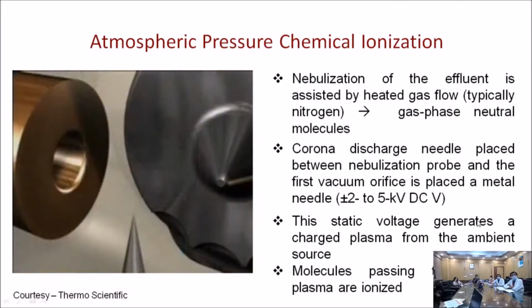In atmospheric pressure chemical ionization, or APCI, the LC eluent enters the source via a grounded capillary and is converted into an aerosol by concentric gas flows. The mobile phase and sample are transferred into the gas phase by rapid heating. Ionization occurs via gas phase ion-molecule reactions initiated by the presence of a corona discharge. APCI is suitable for less polar compounds than ESI, and for molecular weights below 1,000.